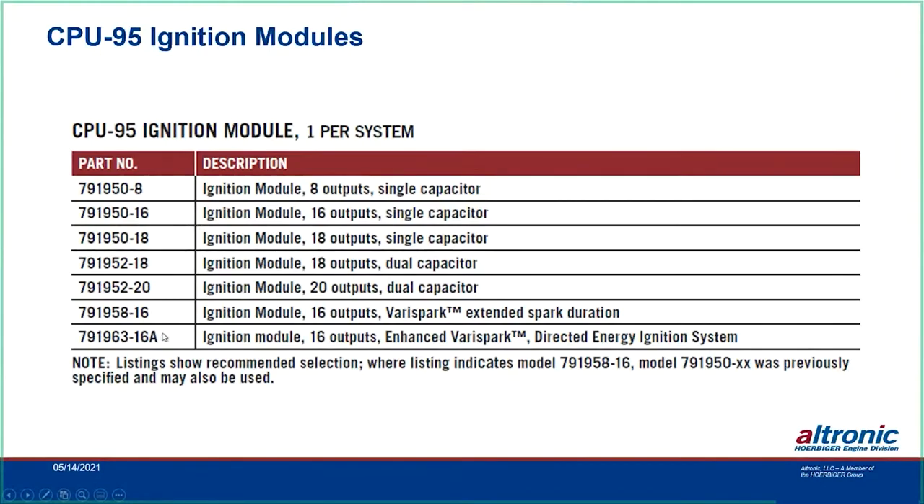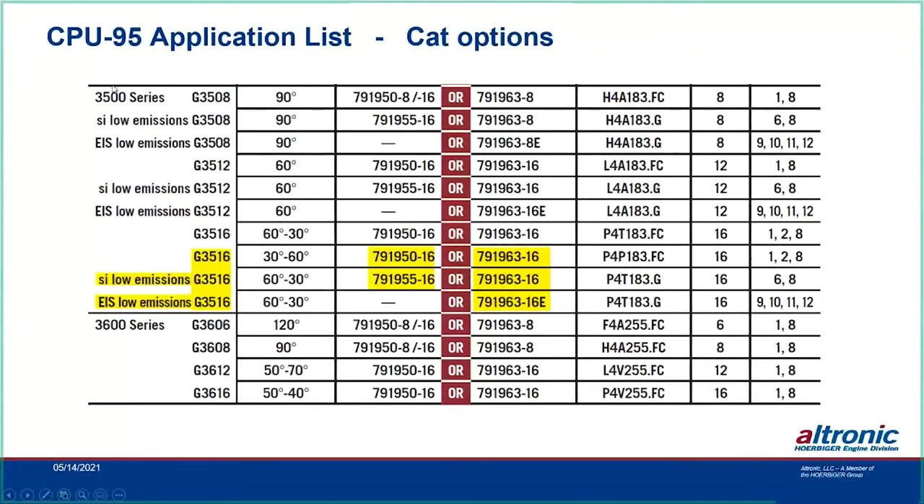In the 3500 series of Caterpillar, there are different options. For a standard 3516 you can use the 950-16 or go to the Enhanced Varispark with the 963-16. For the SI low emissions engine there's the 95C — also called the 95 CAT version — which is the 955-16. For the EIS low emissions engine there's the Enhanced Varispark with the 963-16E. This engine application has the coils under the valve cover. The standard version is the 16A; the 16E has the calibration specifically for those valve-cover coils, and that's one of the latest variations offered in the 95 series.